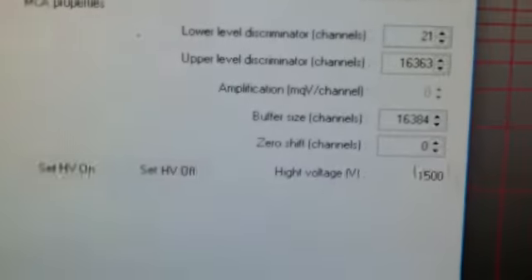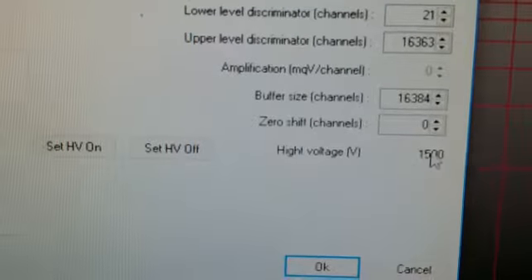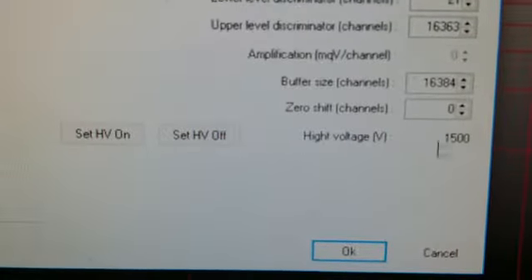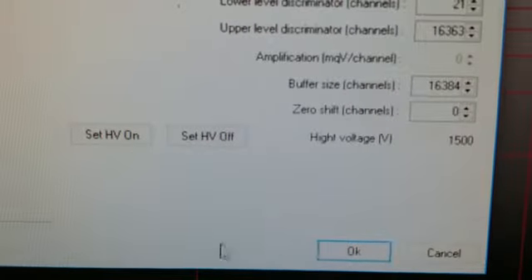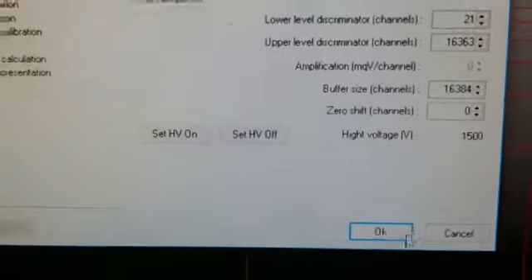And then I am going to look in here, and the voltage should also be reading 1500 volts here, although we have actually set it from the hardware. This is just for you to monitor what the high voltage is. So I am not going to change anything in here. Everything should be as default, and I'm going to say OK. And then I will start my analyzer.